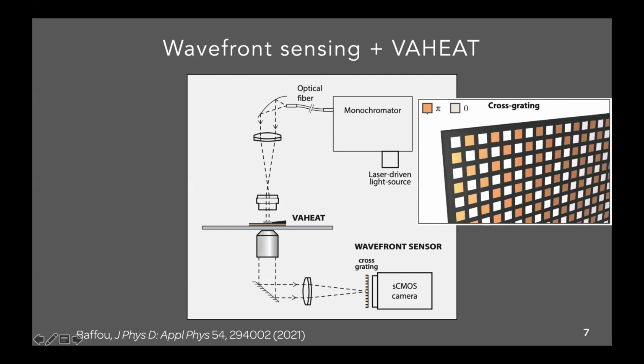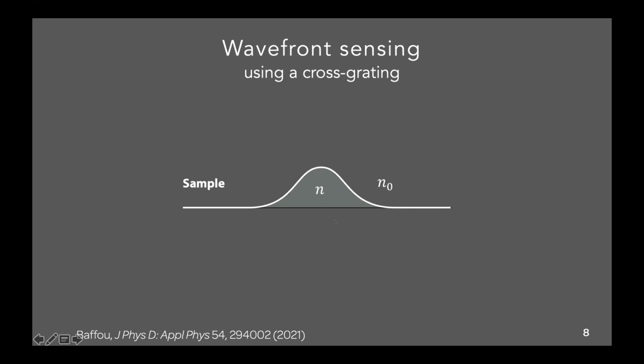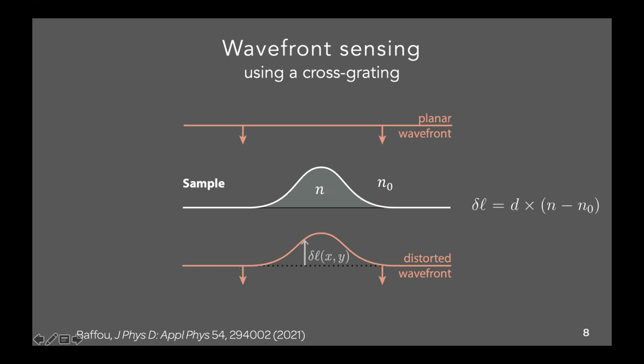So when you do that, I will skip the details, but you can map the wavefront distortion created by your sample. The sample can be any sample, provided you have a non-uniform refractive index. So here, this is a side view. You have an object of refractive index n in a liquid of refractive index n0. You have a flat wavefront, and when it crosses your sample, you have a distortion. And this distorted wavefront, delta L, equals the topography times the refractive index difference. So if you measure the wavefront distortion, you can measure the refractive index, provided you know D, which is the topography of the microcrater, but usually we don't know it.